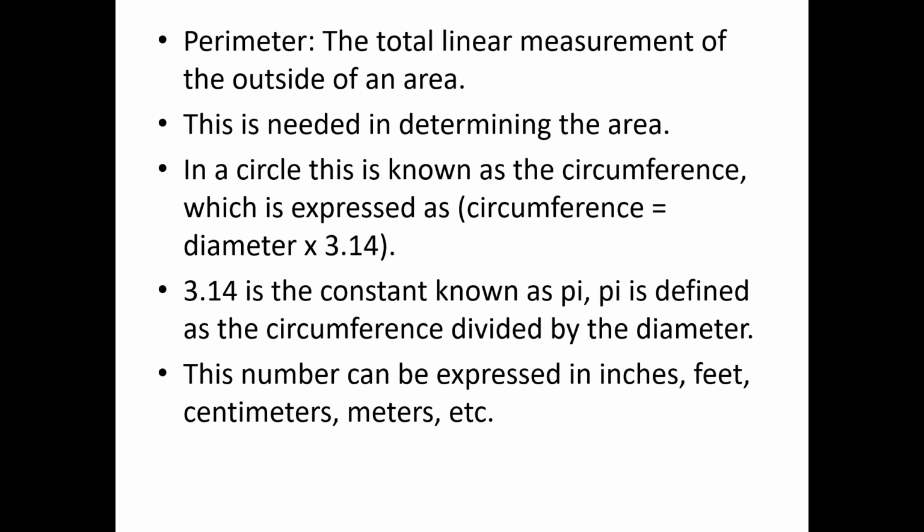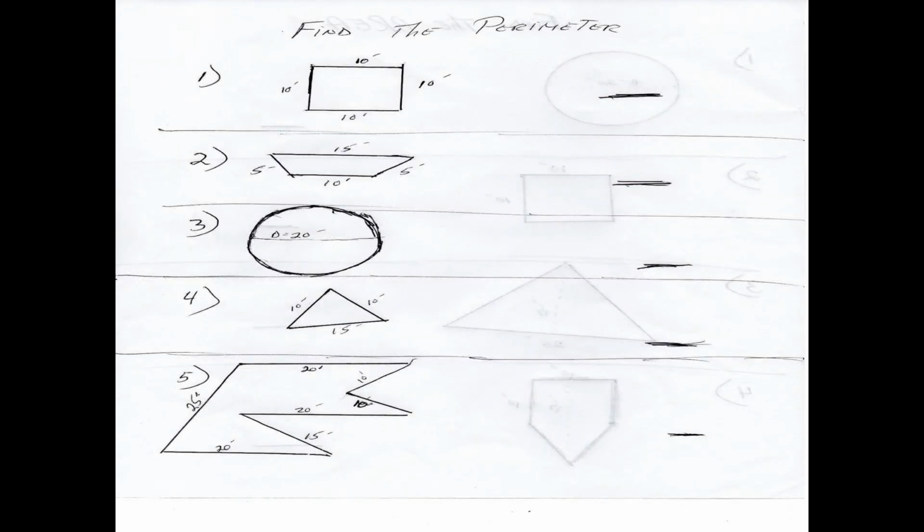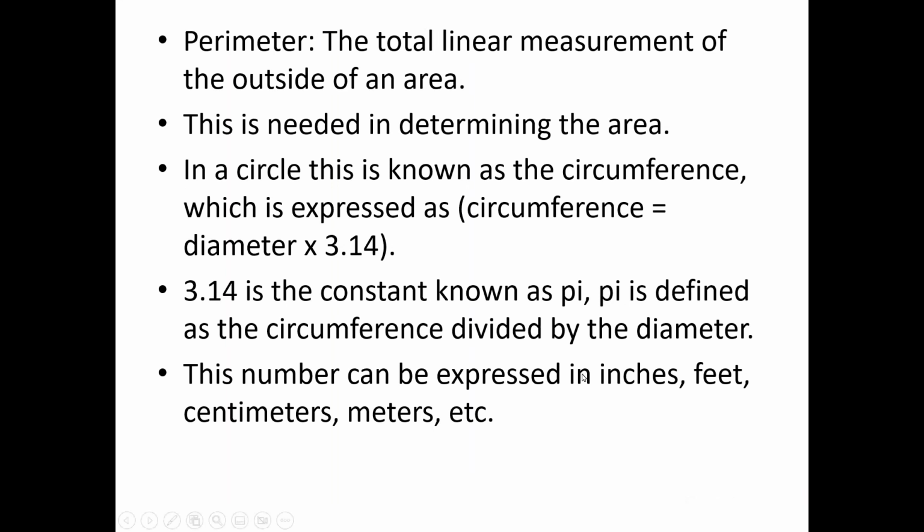One of the other ones is surface loading rate or surface settling rate, which is gallons per day per square foot. But that's the area, the surface area of the tank. That's usually around 1,000, give or take, 1,000 gallons per day per square foot. But these are common loadings for clarifiers. Part of that is the weir length, and it involves a perimeter, especially the perimeter of a circle. And then we'll do these problems next time. Actually, that's all I got. Oh no, I got some perimeters.